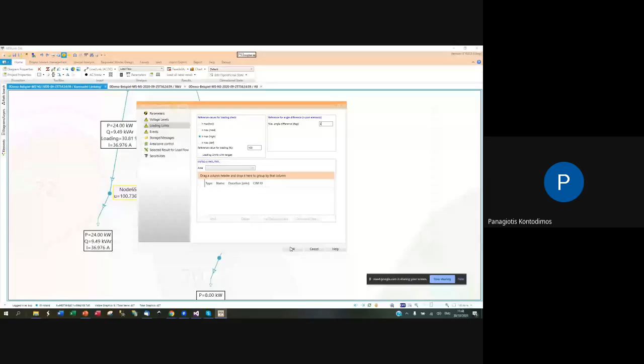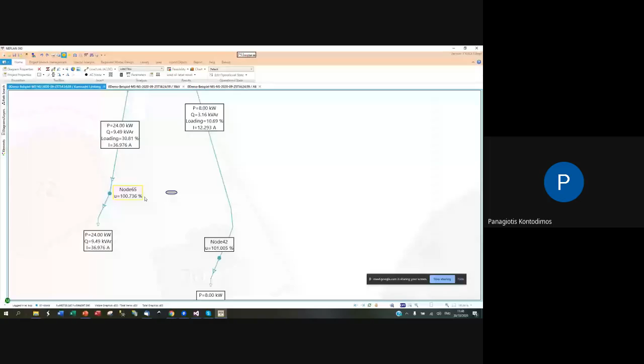If I go to load flow parameters, in loading limits, I can set 5 degrees for angle delta, so it won't show me the angle delta anymore. Now I see my network doesn't have any violations, and this is good.